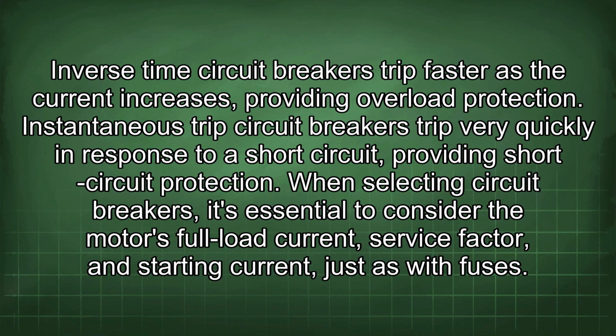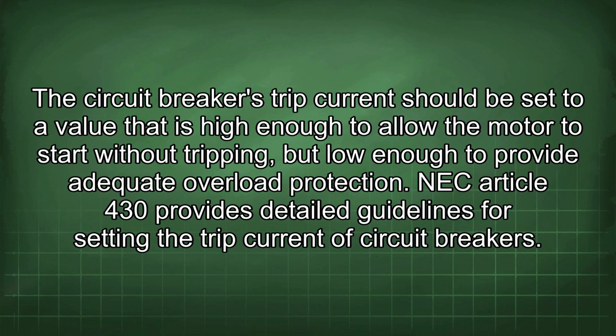When selecting circuit breakers, it's essential to consider the motor's full load current, service factor, and starting current, just as with fuses. The circuit breaker's trip current should be set to a value that is high enough to allow the motor to start without tripping, but low enough to provide adequate overload protection. NEC Article 430 provides detailed guidelines for setting the trip current of circuit breakers.